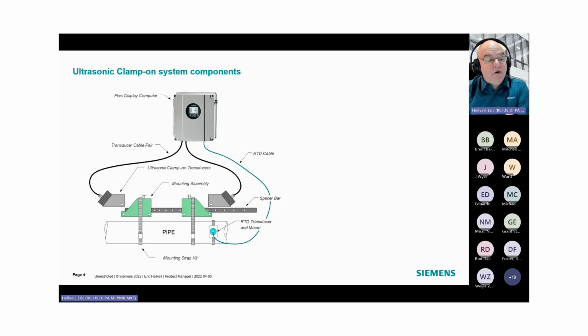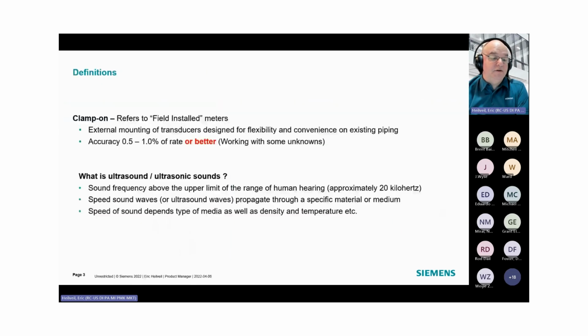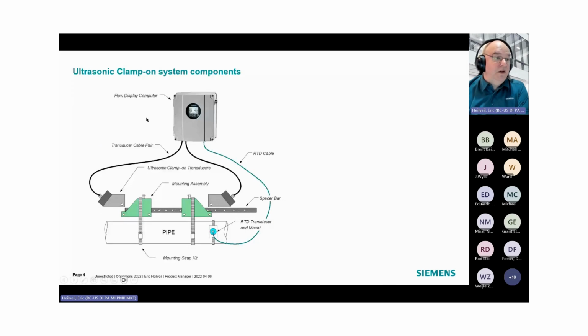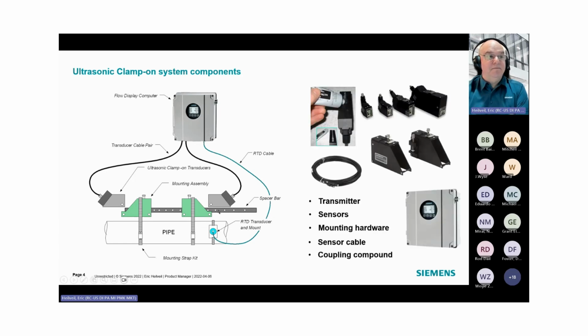Now, when you're looking at a clamp-on ultrasonic system, the fundamental components look like this. You have a transmitter, which is really the flow computer, and its job is to send signals to transducers that are set on a pipe, and then the transducers ring like a bell, and ring the pipe, and the pipe gets a signal injected into it, bounces off the wall of the pipe, and then back to the other transducer that the flow computer actually listens for. So these transducers both send and receive, and the signal just goes back and forth.